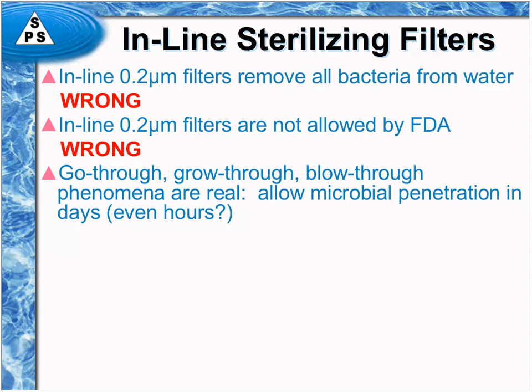Now, even though the filter may be a fraction of a millimeter thick, to a bacterium it's like a gauntlet of 100 yards of trying to make it through, but give it enough time and it will do it. And enough time generally is on the order of a week or two.